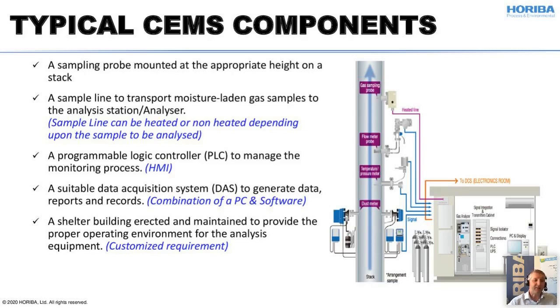Finally, a suitable data acquisition system is necessary to collect and generate the data reports and the records for the CPCBs and PCCs. A shelter building is erected and maintained to provide the proper operating environment for the analysis equipment. This is sometimes required by the customers, but also relevant when we are talking about where the shelter, where the cabinet, where the installation is located. And when we are talking about rainy monsoon season and so on, you might understand that it's not an easy and not a nice workload to maintain the system outside, to stand in the rain, and maybe also to have some other climate conditions than each electrical instrument wants to work in.